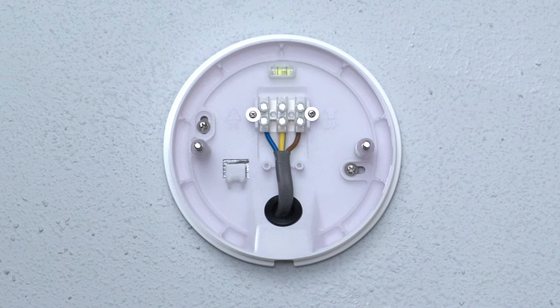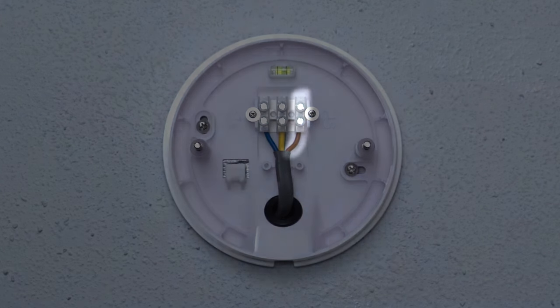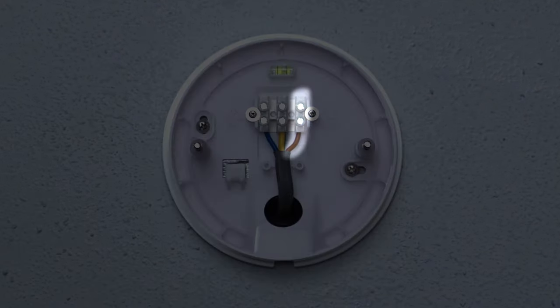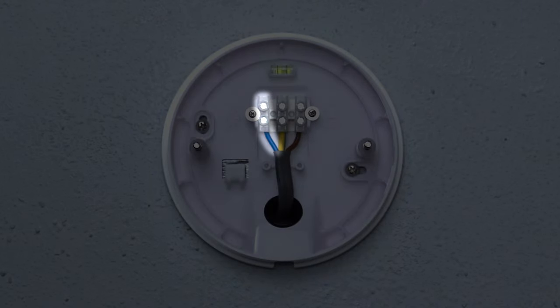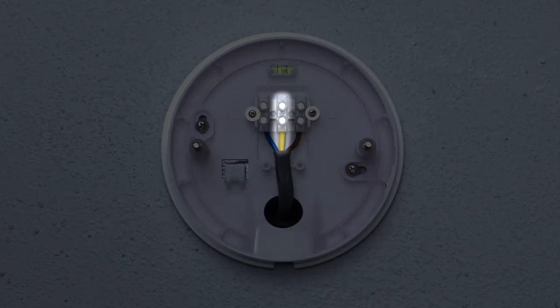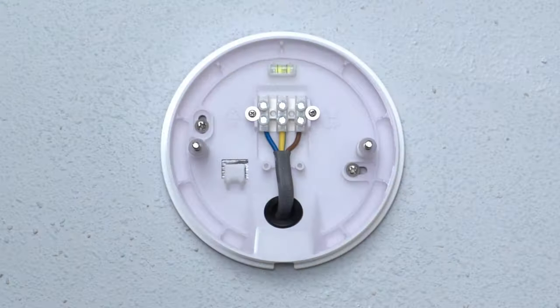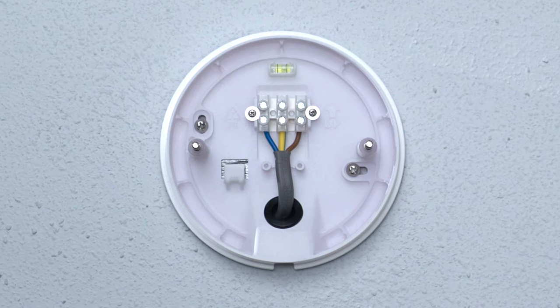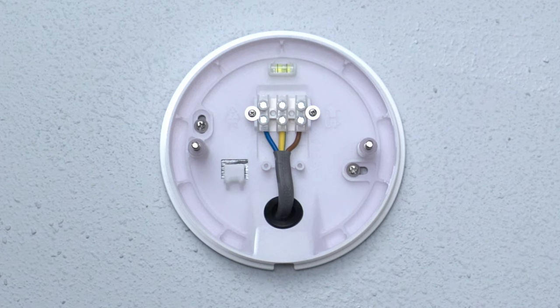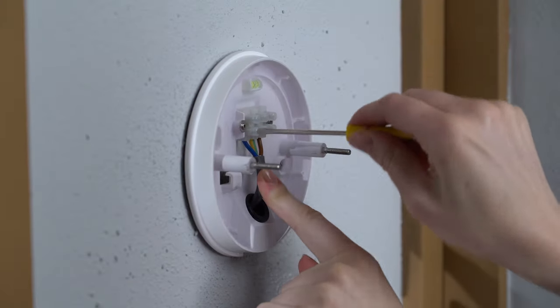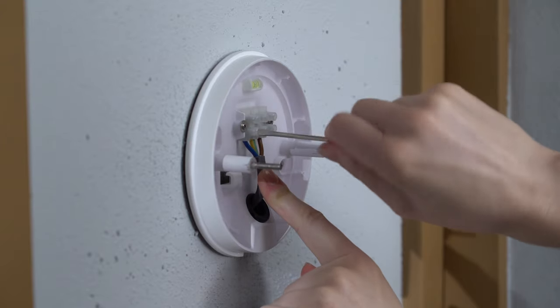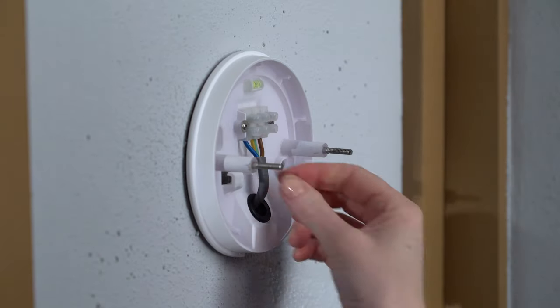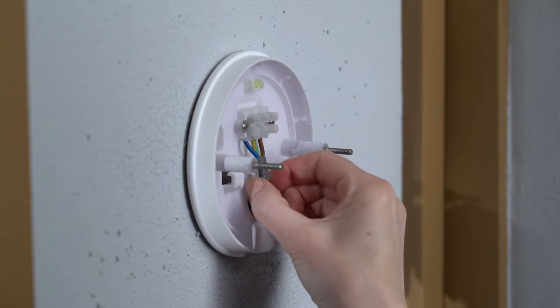With that done, it's time to connect your power wires. Feed your line wire into the L terminal here, your neutral wire to the N terminal, and your sleeved earth wire to the center terminal. No bare wires should be visible. Use the flat head end of the screwdriver bit to tighten each terminal screw. Tug each wire a little to ensure a firm connection.